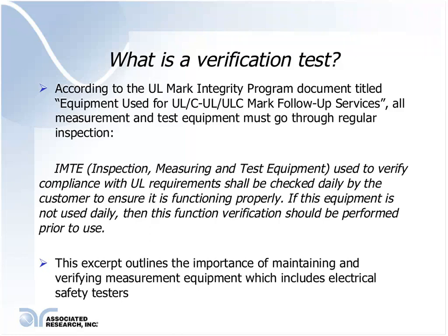If this equipment is not used daily, then this function verification should be performed prior to use. Now, this shows us how important it is and how much importance is given to safety tester verification by standards governing agencies like UL.